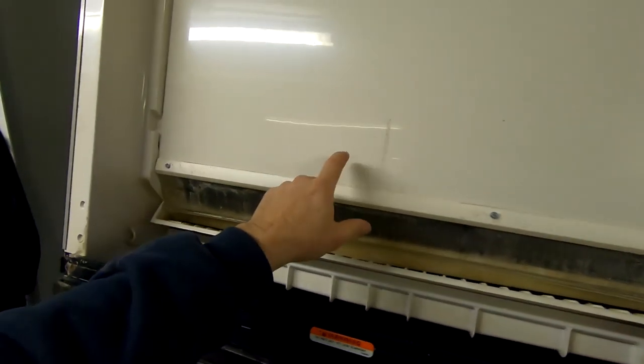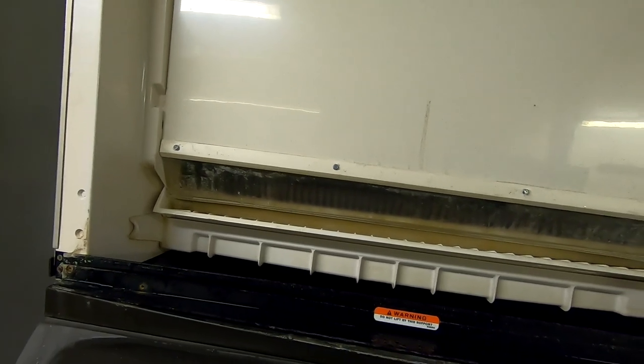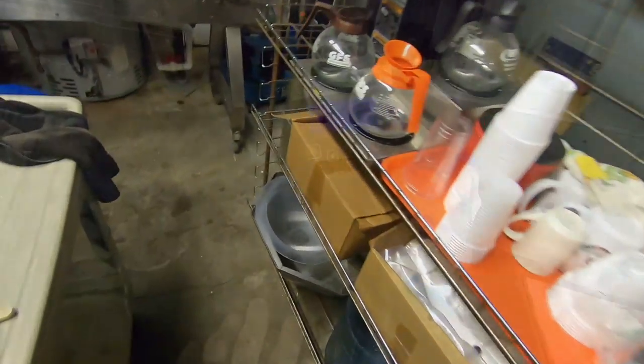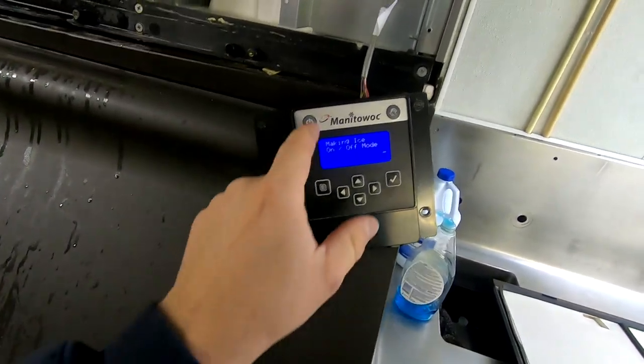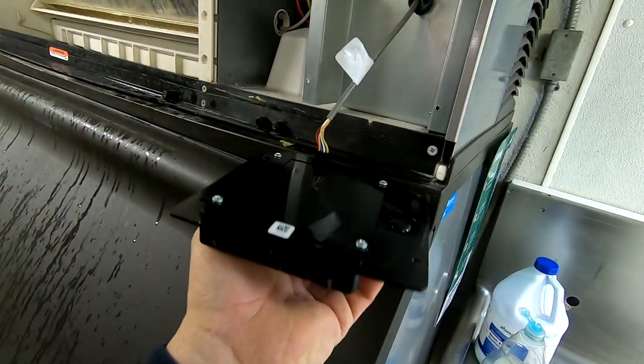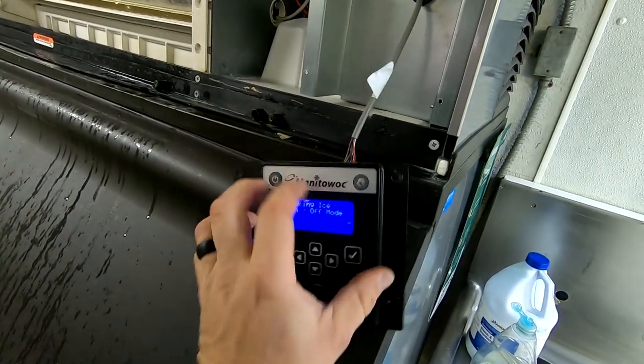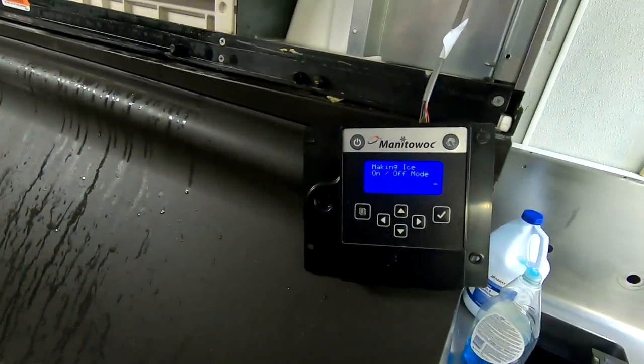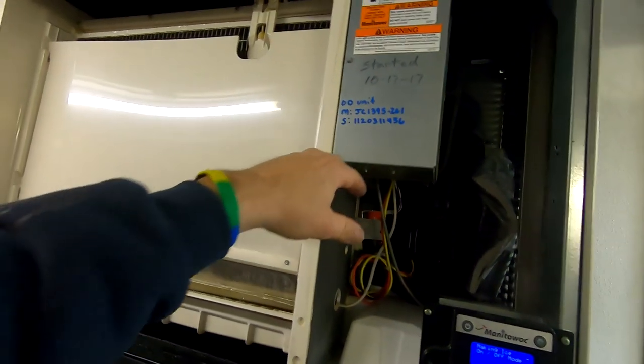So what I'm going to do is I'm going to leave this here so that they can control it. The other controller's obviously acting stupid. We're going to go ahead and order a new shield, and then I'm going to get them a new Square D breaker. Like I said, that keypad comes just as a shell. You'll get that whole shell right there and then you just take the guts out of it and plug it into it.